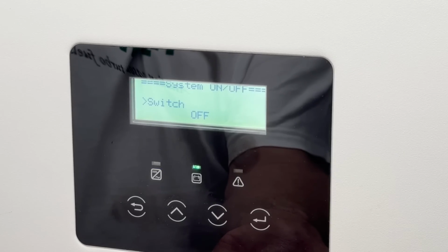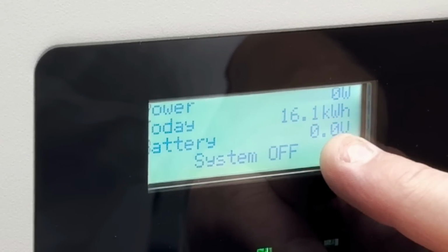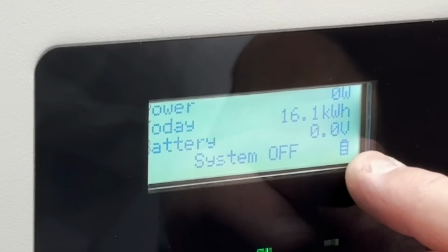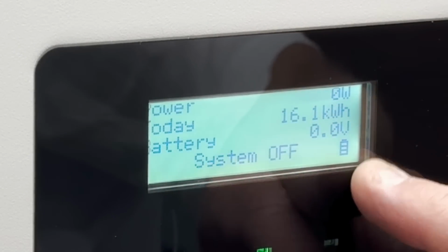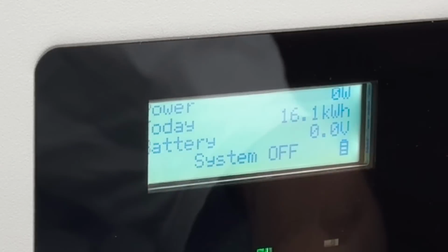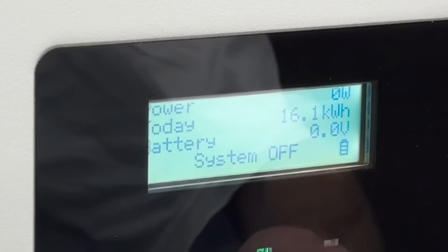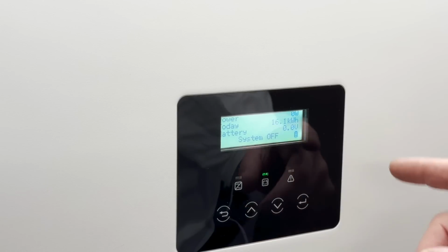So now it's off. You can see that we now have 0 volts, and you can see that the battery is connected in lead acid mode because we don't have anything in percent here. We only have the thermistor connected to the BMS port, and therefore we have this battery symbol.